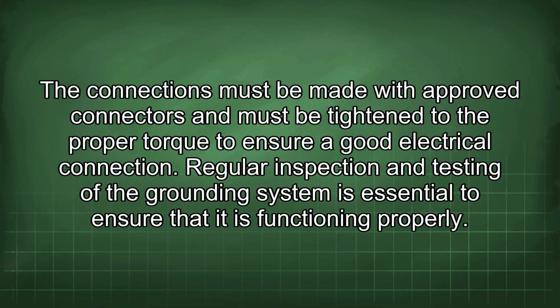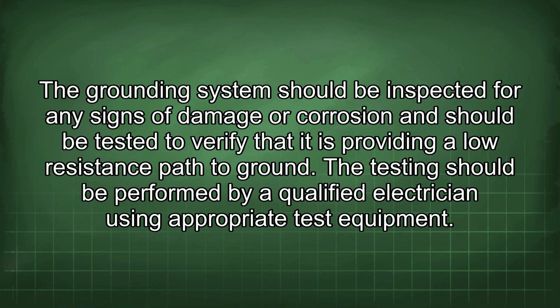The connections must be made with approved connectors and must be tightened to the proper torque to ensure a good electrical connection. Regular inspection and testing of the grounding system is essential to ensure that it is functioning properly. The grounding system should be inspected for any signs of damage or corrosion and should be tested to verify that it is providing a low resistance path to ground. The testing should be performed by a qualified electrician using appropriate test equipment.